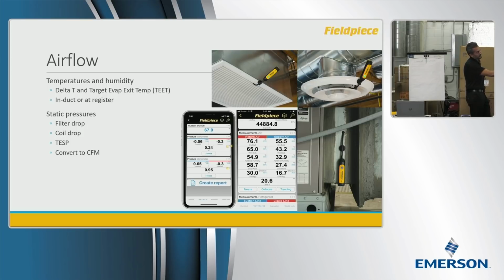So in this scenario here, if the manufacturer is recommending 0.5 inches of water column, we're at 0.95. That's nearly double what it's supposed to be. Okay? So in an ideal world, if it's supposed to be 0.5, we would want to see 0.25 here and 0.25 here, right? On the return side and on the supply side, both 0.25 will give us our 0.5. But we know we're at 0.95. Now, if I only had that information and not this on top, all that tells me is that there's an issue with restriction in the airflow, but it doesn't give me any indication on where to look for that issue.